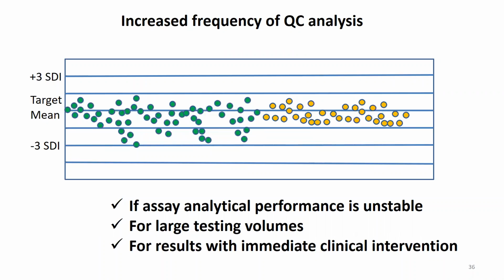Increasing the frequency of QC analysis should be considered if the assay is unstable, like the one shown in the graph. This assay is experiencing a rapid calibration drift. Therefore, we would want to analyze QC more frequently to catch when this happens sooner and implement preventative action, like shortening the time between assay calibrations. It should be noted that manufacturers' recommended QC requirements and calibration frequencies are only minimum recommendations. The laboratory can always choose to run QC more frequently or calibrate more frequently to help keep the assay stable.